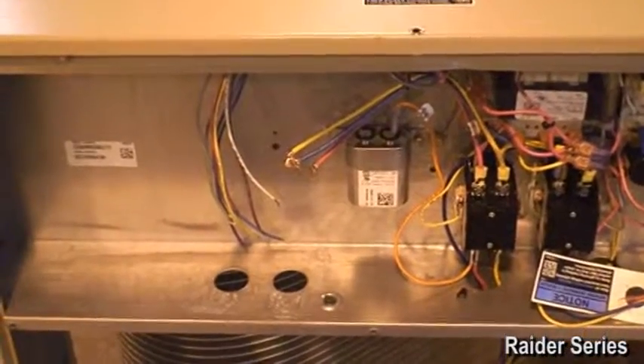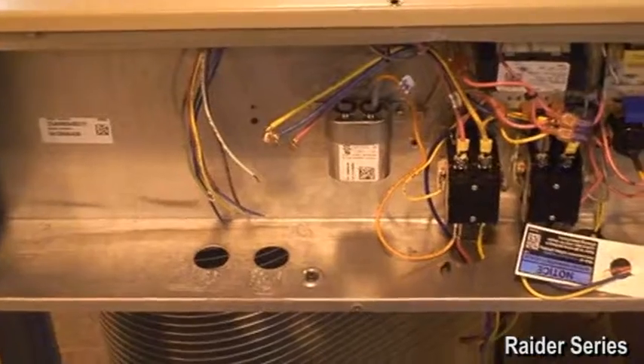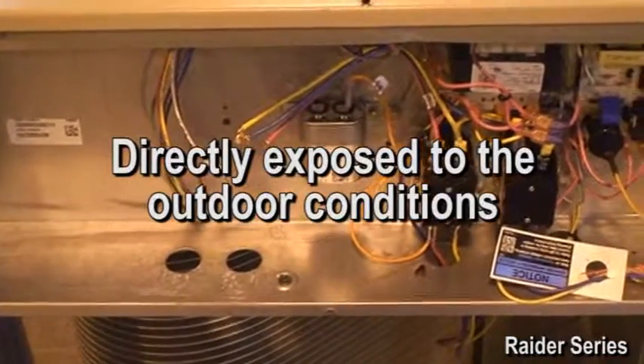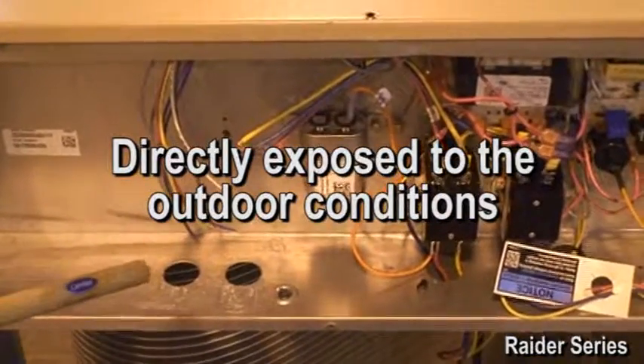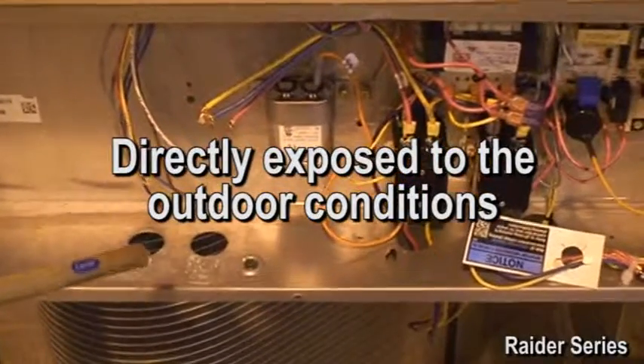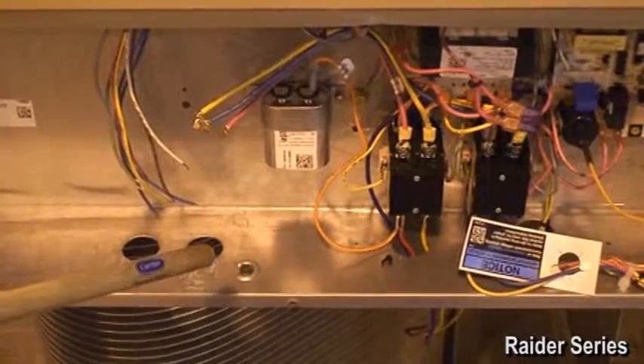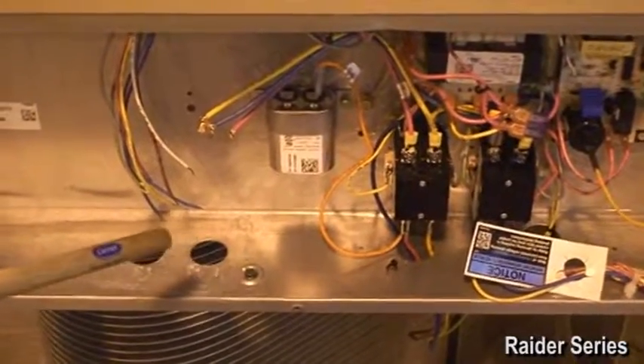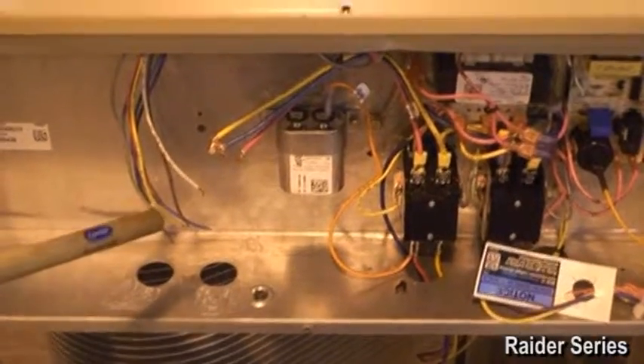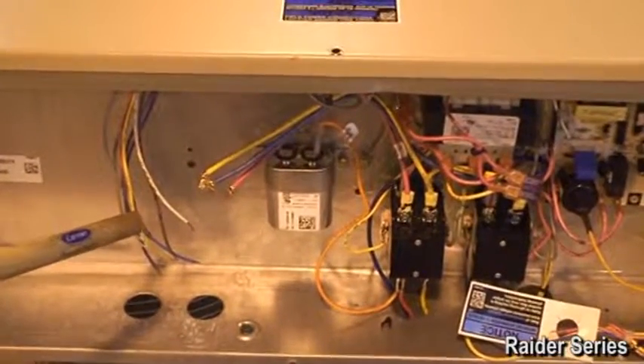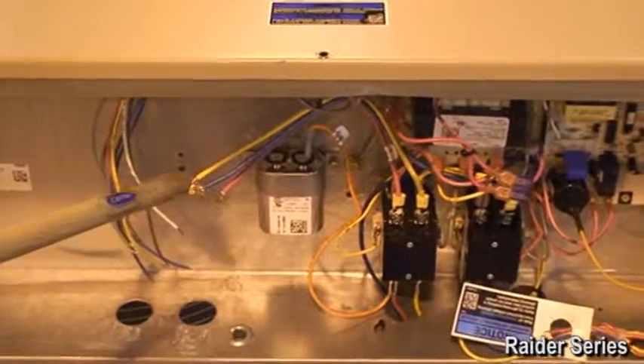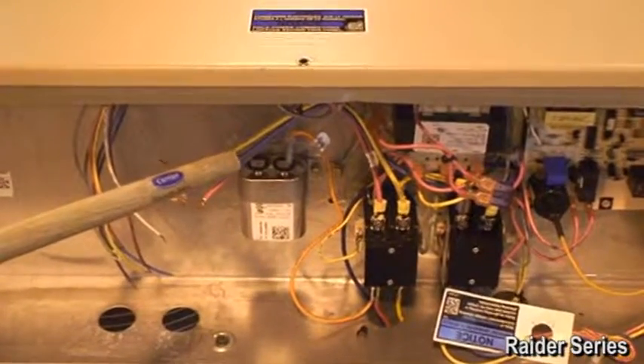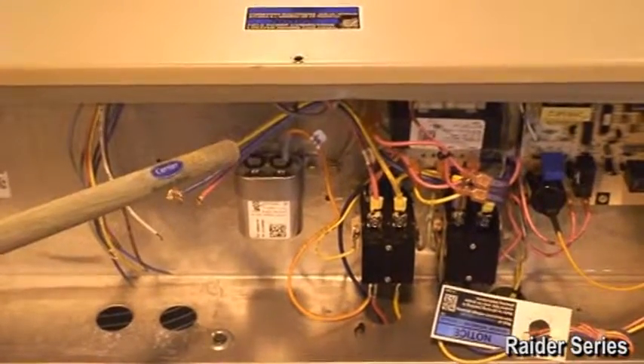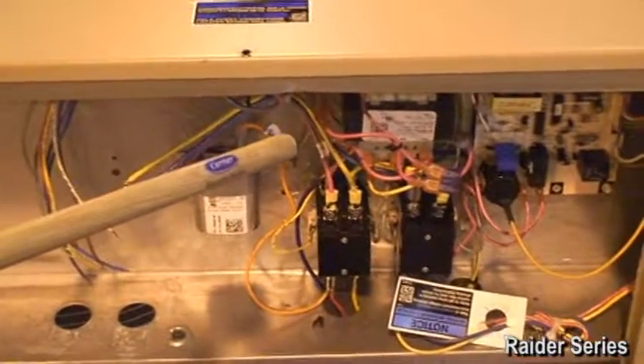Once this single control panel is removed, you will notice that access holes are all directly exposed to the outdoor conditions. The thermostat connections are done directly with wires, not an organized terminal board. Plus, you have the pleasure of providing wire nuts yourself. Also, there will be difficulty in adding field-installed accessories by others. Here are the high voltage connections, same as the low voltage connections.